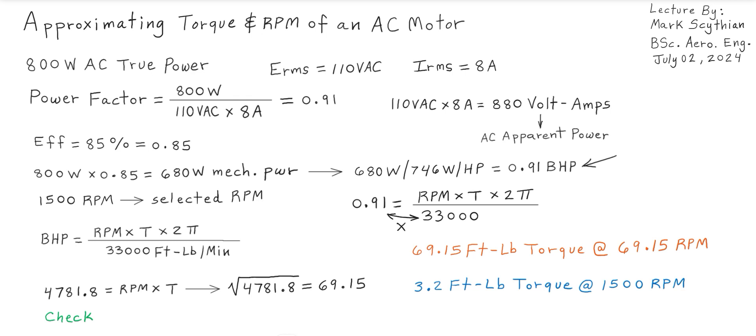So we can check this just to make sure it is accurate. 1500 RPM times 3.2 foot-pounds torque times 2π divided into 33,000. We get 0.91 BHP verified, which is correct.